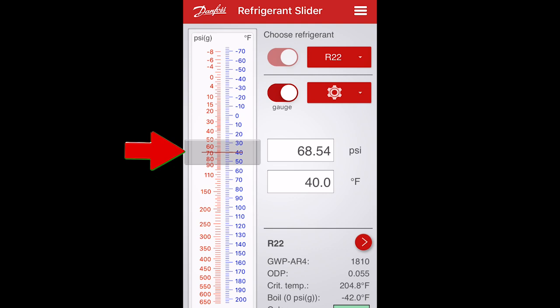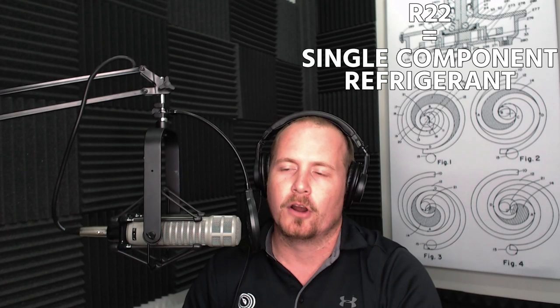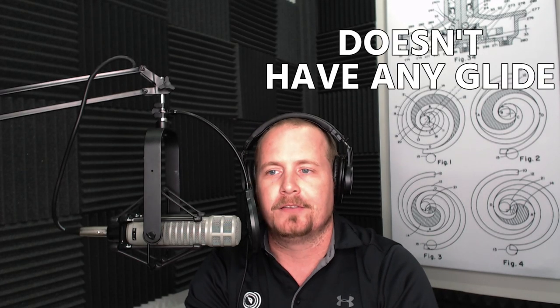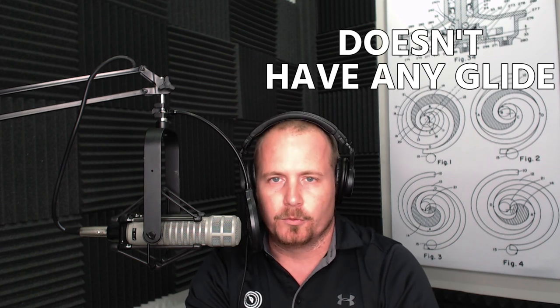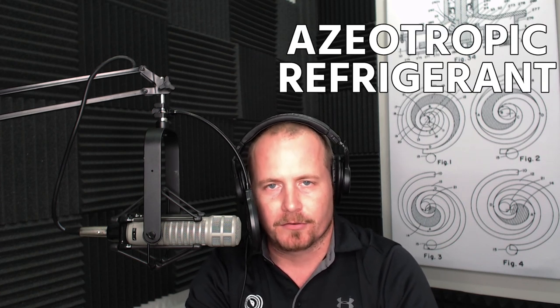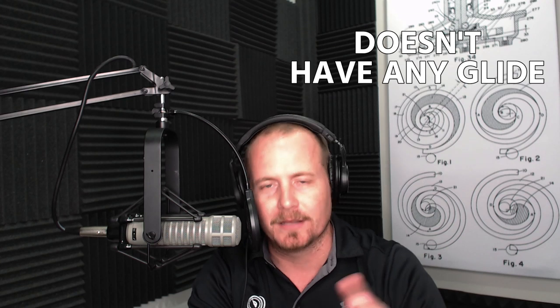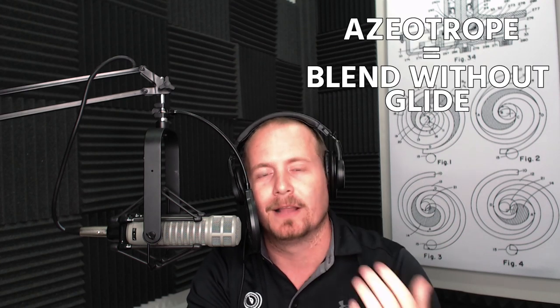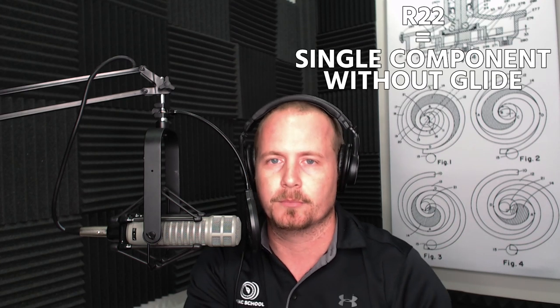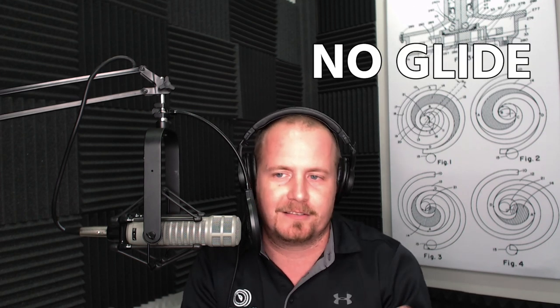And on the refrigerant slider app, you can see up top next to choose refrigerant, there is no option for switching between dew and bubble. So that can't be changed. The reason is because R22 is a single component refrigerant, and so it does not have any glide. Now, really, an azeotrope would be a blend that has no glide. R22 is a single component, so it has no glide. So don't get the terms confused there, but it's glideless. It's got no glide, right?